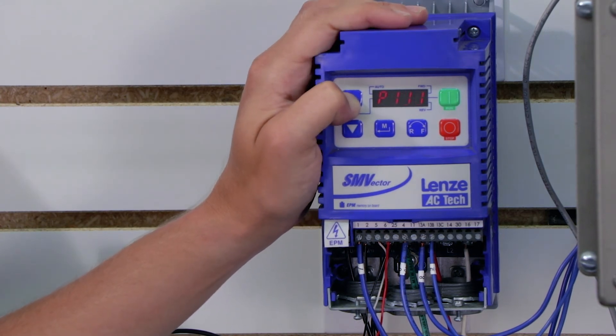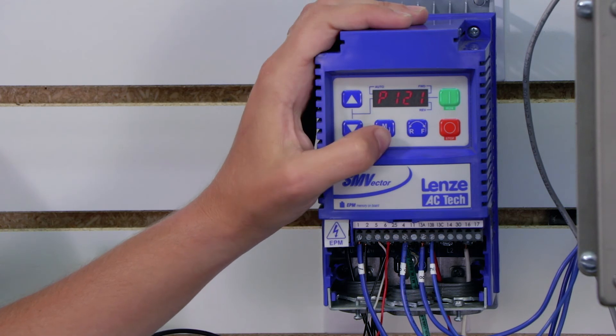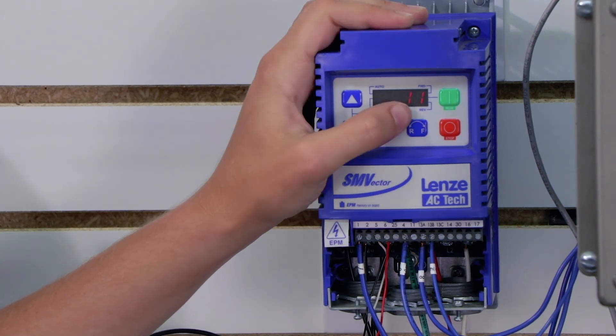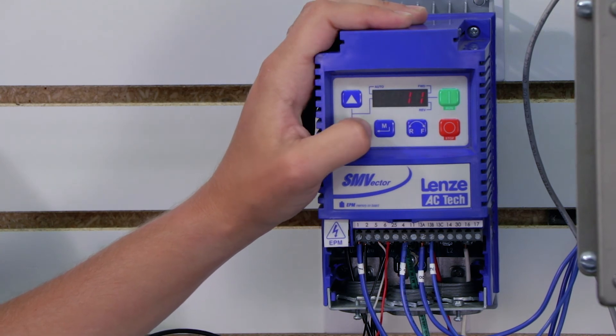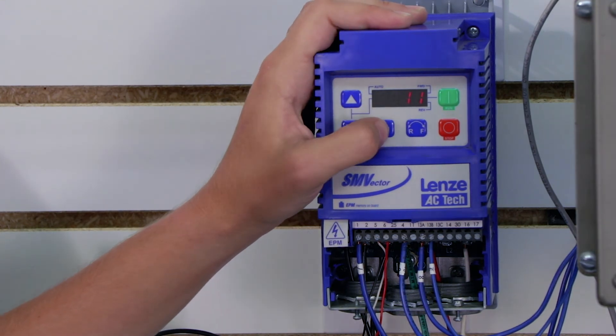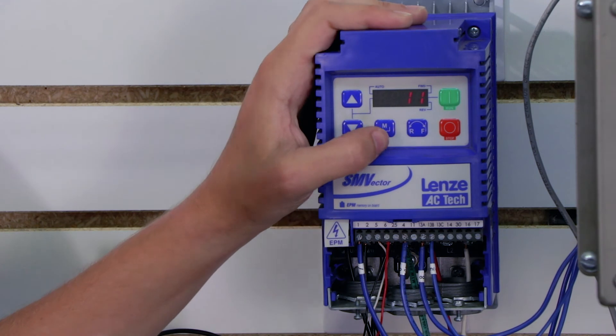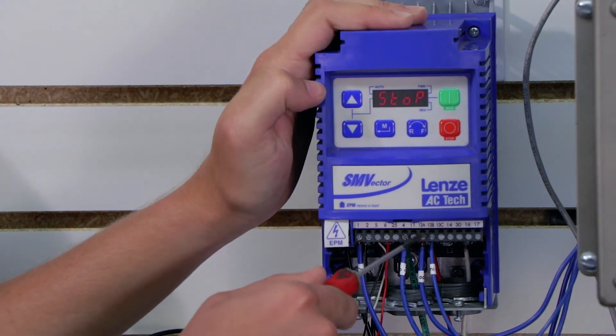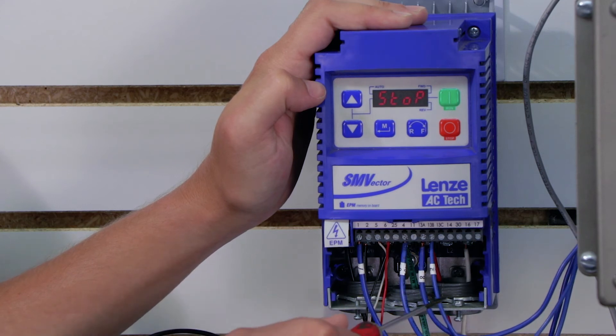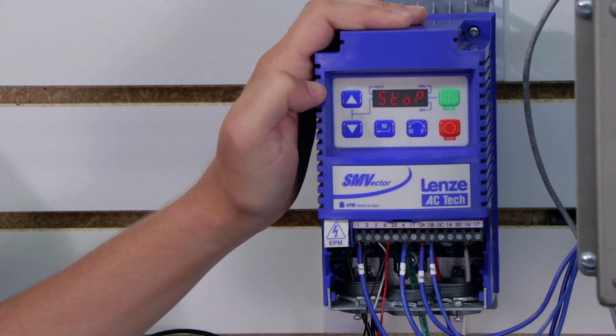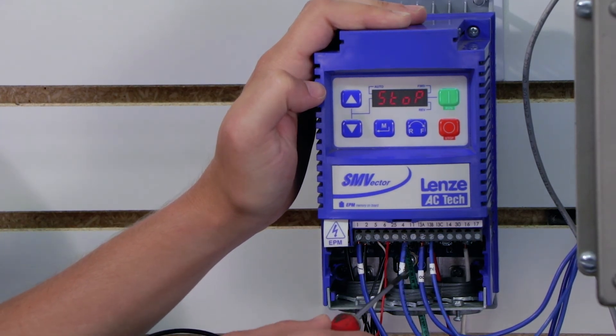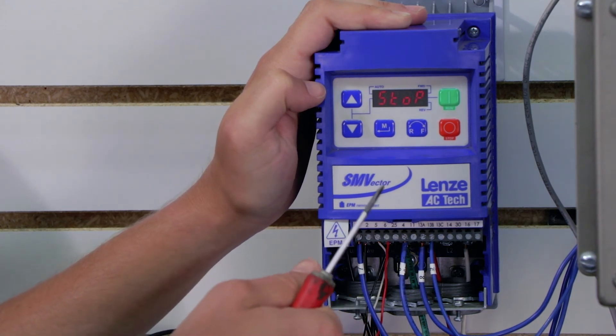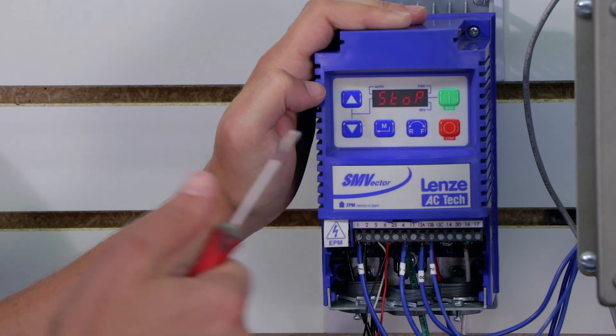So I'm going to go up to parameter 121. This program's 13a, and right now I have it set to 11, and that's actually where I want to set it. The default is 0, so I'm going to set it to 11, which means start forward, which means if there's a momentary connection between 4 and 13a, start running forward. And I say momentary because that's important.